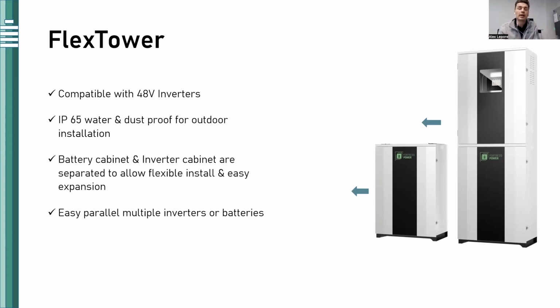What I'd recommend, Chuck, is you can install this outside, but you'd want to maybe not install it in direct rain or direct sun. As general guidance, keeping it out of direct sun will keep it maybe 10 to 15 degrees cooler during the summer, since you're not getting the direct sun. Then there are different ventilation tactics you can use. I wouldn't be too concerned about that - again, we have that quarter-inch thick aluminum which dissipates heat evenly to support the batteries, and there's a ventilation fan on the inverter itself.